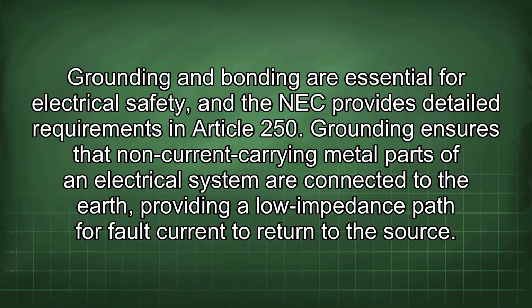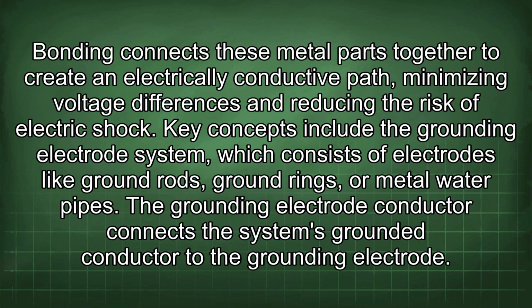Grounding and bonding are essential for electrical safety, and the NEC provides detailed requirements in Article 250. Grounding ensures that non-current carrying metal parts of an electrical system are connected to the earth, providing a lower impedance path for fault current to return to the source. Bonding connects these metal parts together to create an electrically conductive path, minimizing voltage differences and reducing the risk of electric shock. Key concepts include the grounding electrode system, which consists of electrodes like ground rods, ground rings, or metal water pipes. The grounding electrode conductor connects the system's grounded conductor to the grounding electrode.